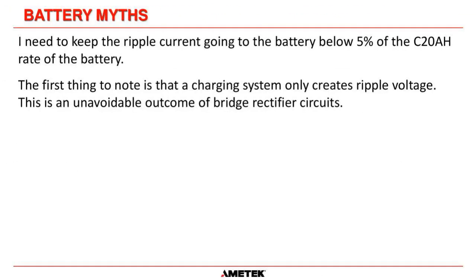Oh boy, I am running out of time, and this is a good one. I need to keep the ripple current going to the battery below 5% of the C20 ampere hour rating of the battery. Okay? This is so common. And we'll go into why it's a little bit of a misconception. The first thing to note is that the charging system only creates ripple voltage, and that is an unavoidable outcome of bridge rectifier circuits or charger circuits.